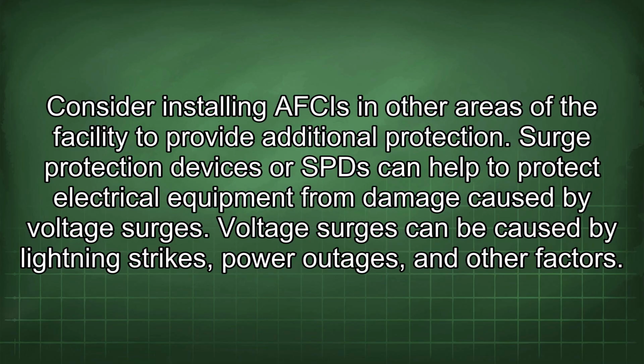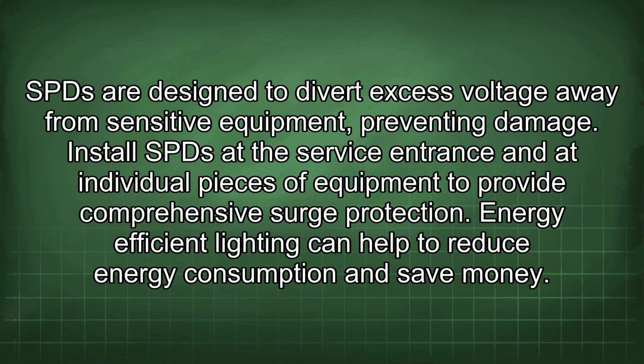Surge protection devices, or SPD, can help to protect electrical equipment from damage caused by voltage surges. Voltage surges can be caused by lightning strikes, power outages, and other factors. SPD are designed to divert excess voltage away from sensitive equipment, preventing damage. Install SPD at the service entrance and at individual pieces of equipment to provide comprehensive surge protection.